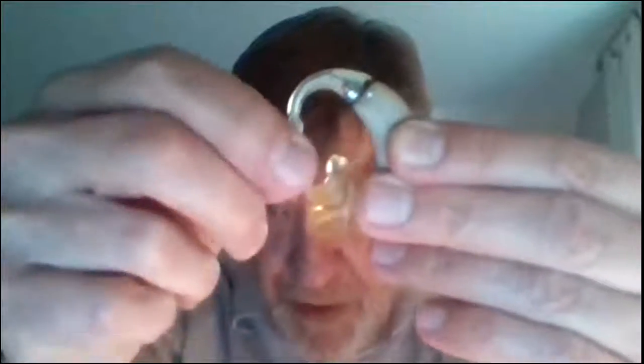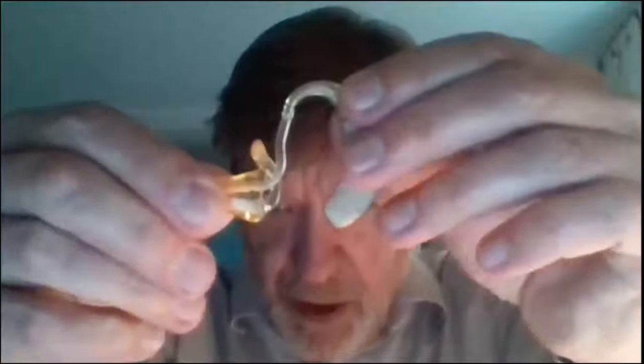Now let's look at the pieces and parts of a hearing aid. Okay, you open up the battery door, close it. You got an on-off switch. You have a volume control on the hearing aid, and you open this up, and you'll see a tiny little microphone. Let's see if I can show you that. There, see that little dot? That's a microphone. That's what's picking up the sound. The hearing aid makes it louder, and then pushes the sound through this ear hook, through this tubing. This is a tube, and then this is the ear mold.